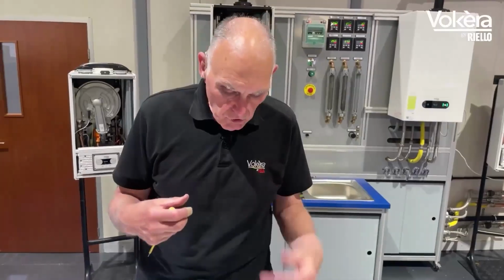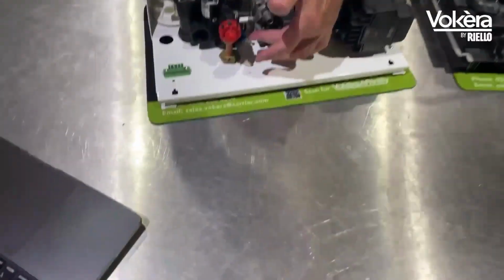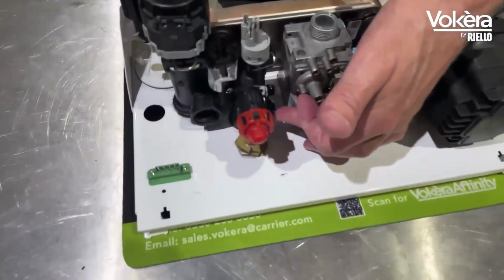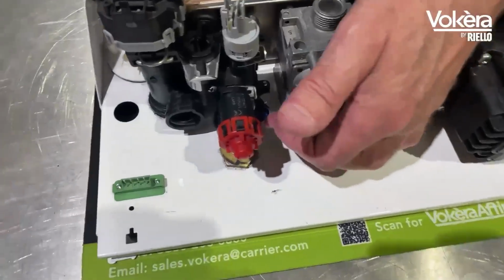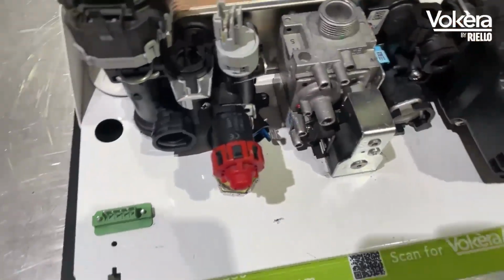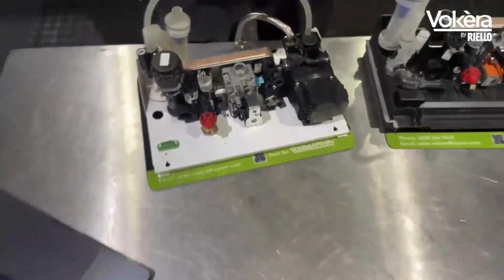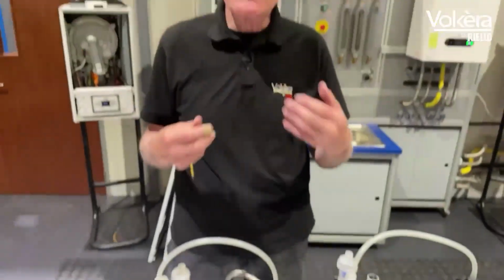However, the boiler software doesn't want the end user to go without hot water, so it ignores a faulty domestic hot water thermistor when someone opens a hot tap, and runs the boiler at 65 degrees on the main heat exchanger thermistor, so the customer has warm or hot water until the problem is fixed.